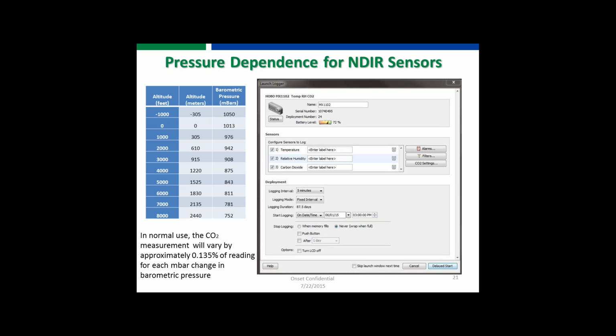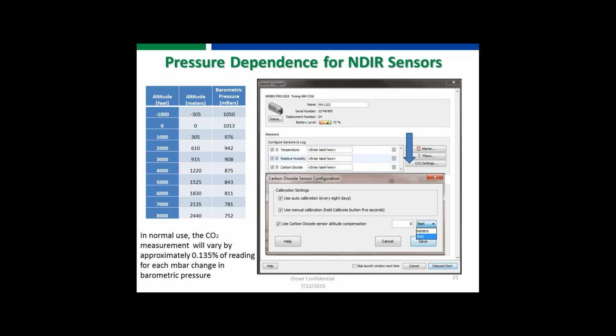And here's a screenshot from HOBOware. This is the launch screen in HOBOware. You can see there's a button called CO2 settings, and when you press that, this is where you would go in and either check or uncheck your auto cal or your manual cal, or select to use your carbon dioxide altitude compensation, and you put that number in either feet or meters.